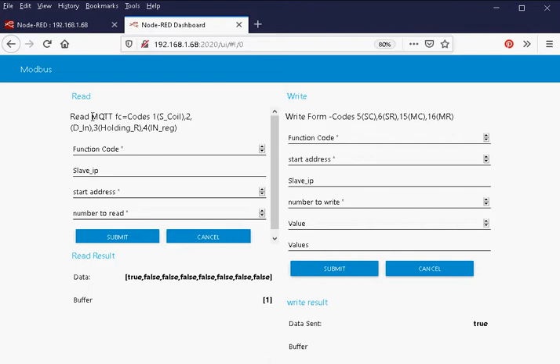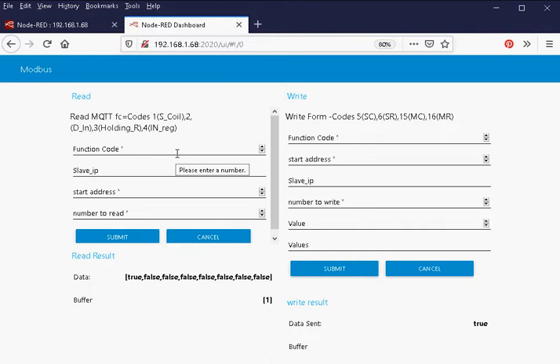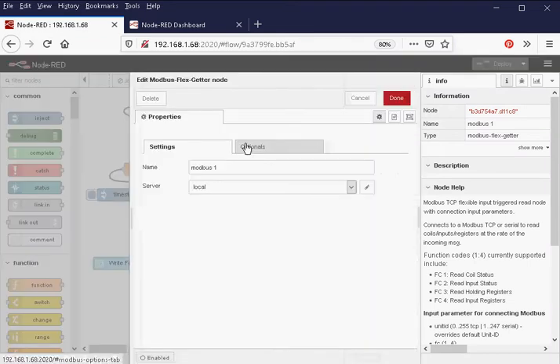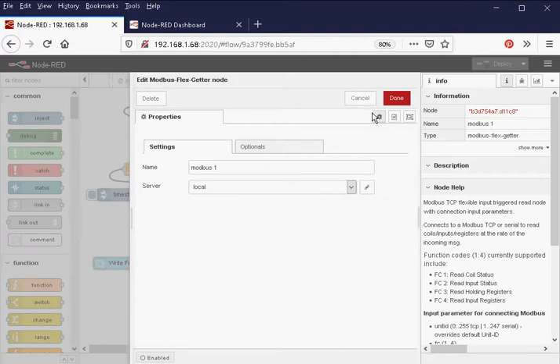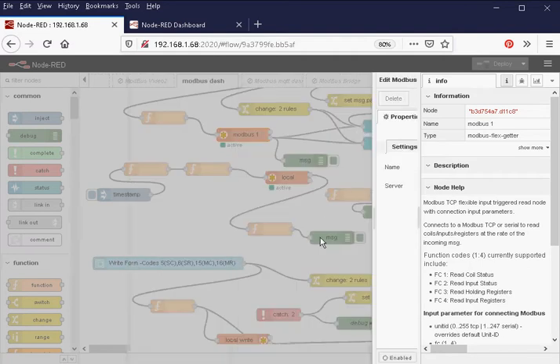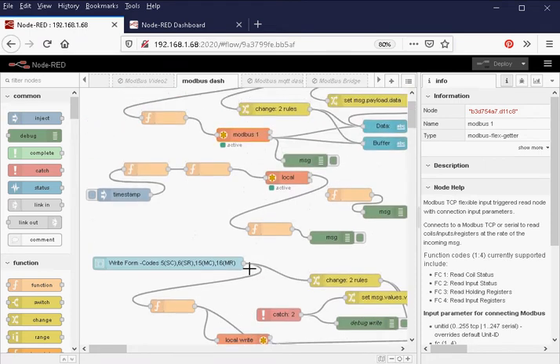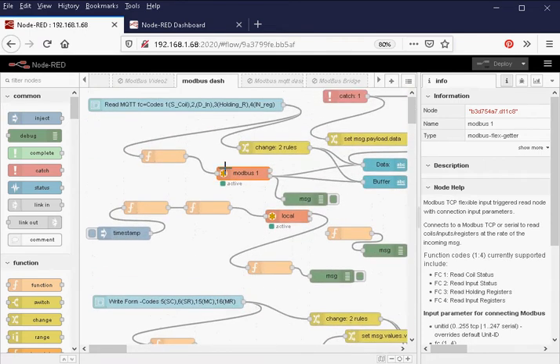So we have read and write, so we can write to Modbus and read from Modbus. I didn't cover coils in the previous videos, but the coils are exactly the same as registers, except that we're only dealing with one bit. All you do is set a different function code. You use exactly the same nodes here, so we just use the flex getter to read and the write node to write exactly as we did with registers. The only difference is the function code and the values we pass to it.